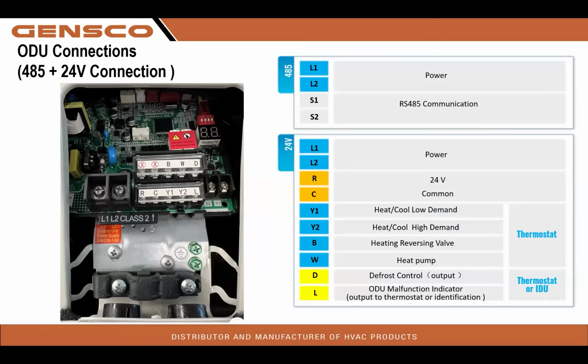Another look at our 485 and 24-volt connections out at the outdoor unit. There's our S1, S2, if we're going to be fully communicating, and our 24-volt. And our 7-segment display right there.